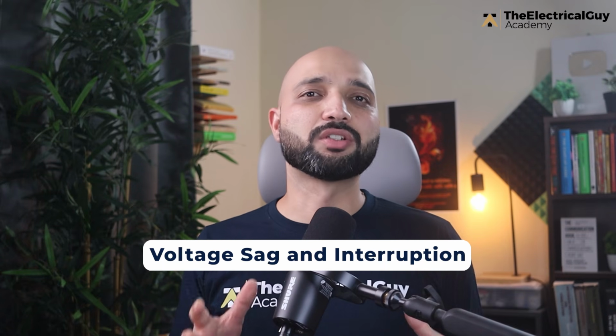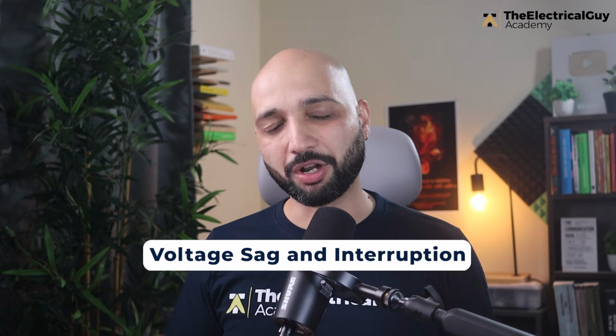line stops. Now, the question is, if power was not completely gone, why did the machine stop? This is where voltage sag and voltage interruption become important. In many industrial plants, the real problem is not always a blackout. Sometimes a voltage dip lasting only a few cycles is enough to disturb sensitive equipment and stop an entire process. So in this video, we'll understand what voltage sag and interruption are, why they happen, how they affect electrical systems, and what practical solution can reduce their impact.